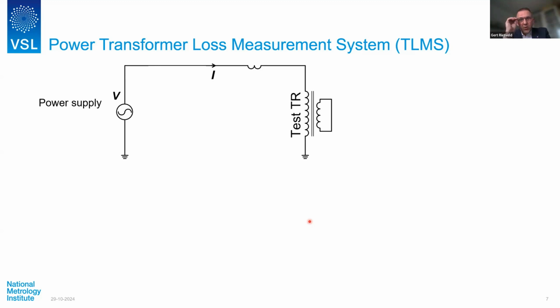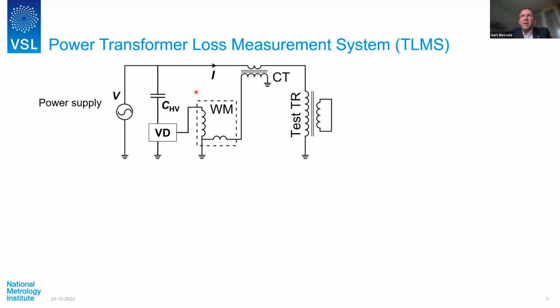And this is the way this loss is measured. So you have the test transformer here, you have a power supply, you apply a voltage, and you measure the current that is running. Well, a rather straightforward approach. And then, the voltage is in the kilovolt range, the currents are very high.